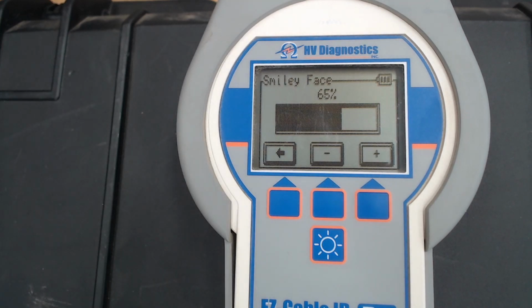So what that does is when I go to calibrate, say, for example, I get 10 amps when I calibrate. When I go ID at my cable, it's looking for the unique signal, and it's also looking for at least 65% of that 10 amps. So I need at least 6.5 amps and that unique signal to give me the smiley face. If I got the unique signal, but I only got 1 amp, it's not going to give me a smiley face because I don't have 65% of the current that I calibrated with. That can be adjusted.